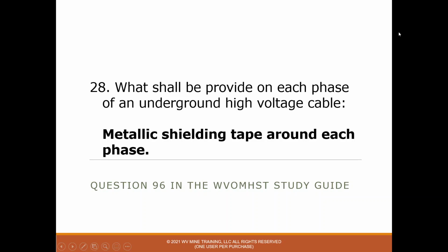On high voltage, it's certainly a safety feature, but another thing is that high voltage does weird stuff. You'll actually have a force field around that cable, and this shielding tape blocks that force field. I think if you don't have that metallic shielding tape around the high voltage cable, that electric force field will eventually destroy the insulation on that cable. So the metallic shielding tape on the high voltage cable is a safety feature as well as protecting the insulation of the cable.